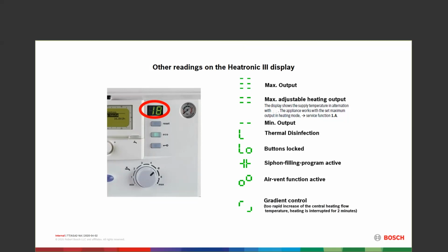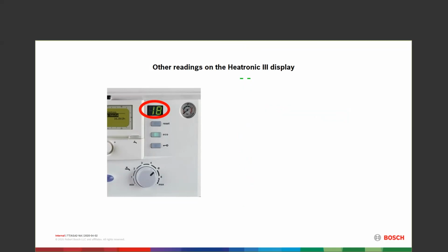Mostly on systems that are piped incorrectly, where we have zone valves that might shut down before the call for heat does, that type of thing, where we shut the flow off and all of a sudden our boiler loop is increasing so quickly, or our system side is also increasing so quickly, it will shut it down for a couple of minutes.